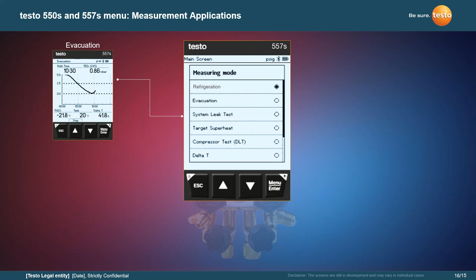For evacuation, using the vacuum probe, you have the evacuation option built into that probe. Then there's the pressure leak test, used anytime you're pulling a system down and want to pressurize it with nitrogen to check the decay or how well it holds. You can do this without any other smart probes, since everything's built into the manifold.